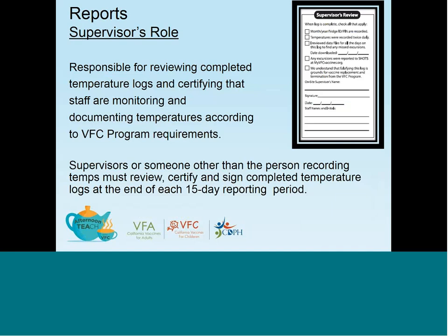Let's take a moment to discuss the importance of the supervisor's role regarding reports. Supervisors play a vital role managing vaccines and are responsible for reviewing completed temperature logs and certifying that staff are monitoring and documenting temperatures according to VFC program requirements. For the California VFC program, a supervisor is someone other than the person recording the temperatures, and they must review, certify, and sign completed temperature logs at the end of each 15-day reporting period.